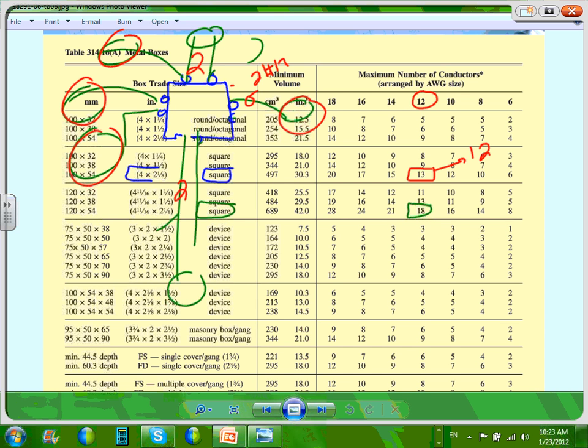So you start right here. If I want to bring an EMT conduit and feed from it, put a J box here. 1, 2, 3, 4, done. Move on. Some fixture wires, guys, have a smaller wire size, so might give you an advantage, like number 14 and so forth. Any question about this? Any question?